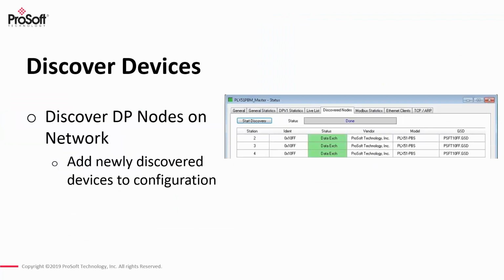Additionally, from a Profibus DP master perspective, one of the features that for us has been very helpful is the ability to do a discovery. This allows you to essentially plug a module on the network with a bunch of other devices, and it's going to come back and tell you what devices are on that network, what their ident number is, or their unique identification number on the Profibus network, and any corresponding GSD files associated with those devices.